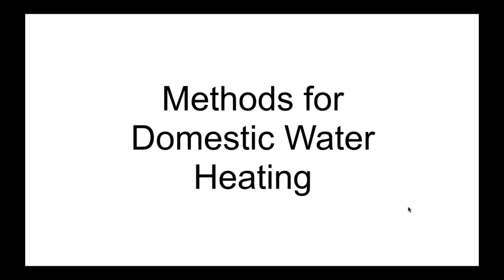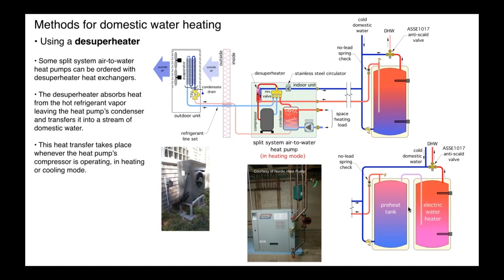Now, of course, residential hydronic systems, most of them include domestic water heating. So how can you do this with an air-to-water heat pump? Okay. Well, one approach is to use a desuperheater. Now, many geothermal heat pumps have this, whether it's a geothermal water-to-air heat pump or a geothermal water-to-water. What a desuperheater is, is an extra heat exchanger that takes the hottest gas coming off the compressor before that gas gets to the reversing valve, and it passes through the primary side of a heat exchanger.